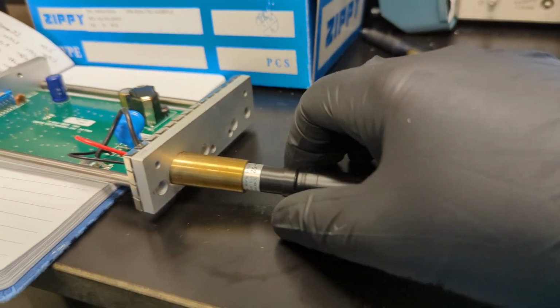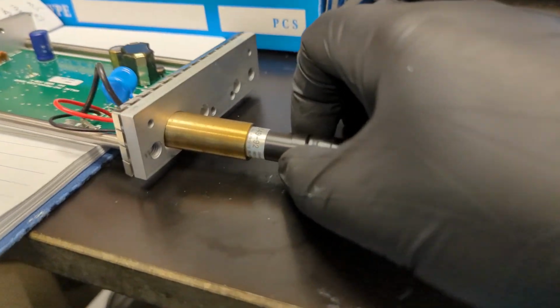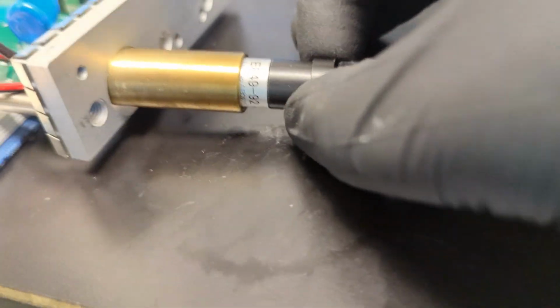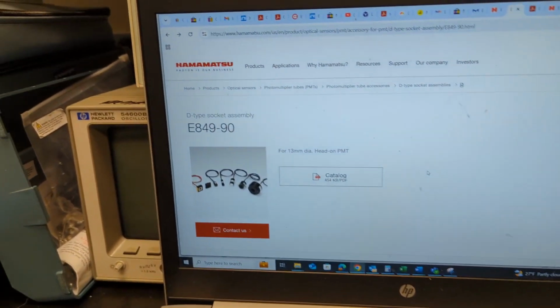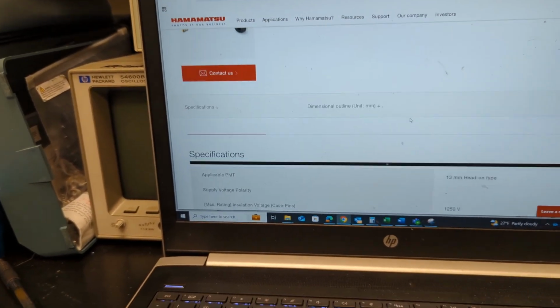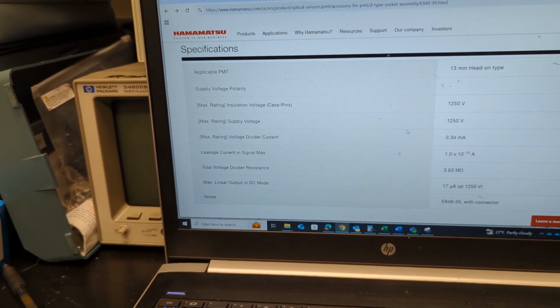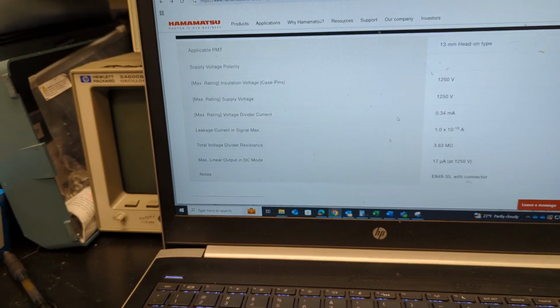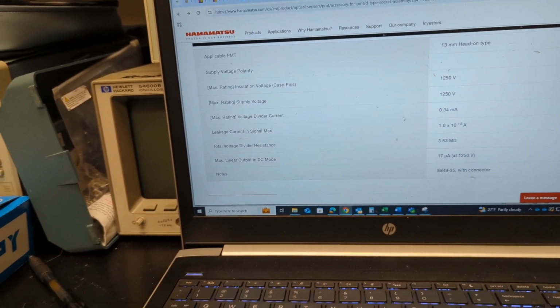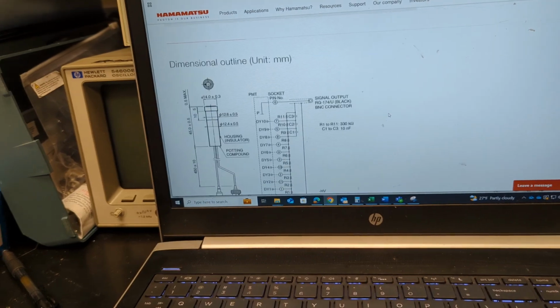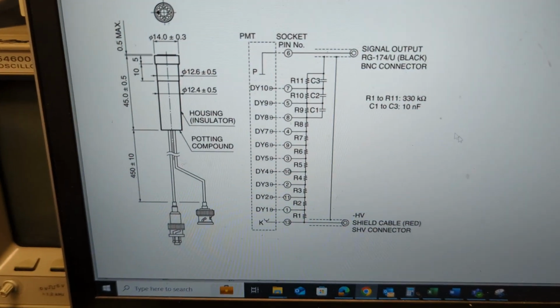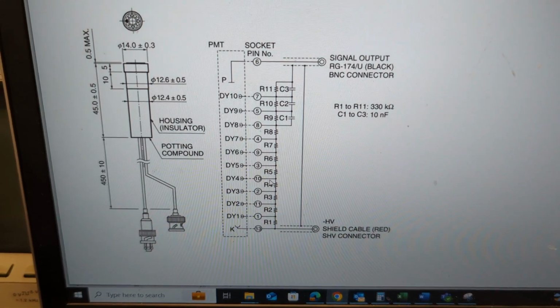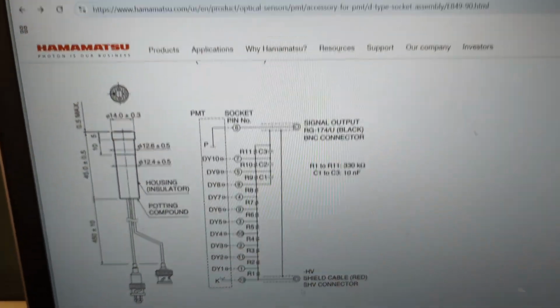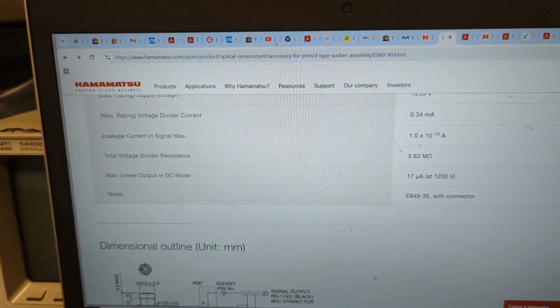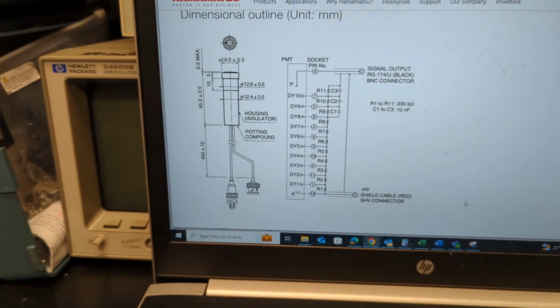you'll notice though that you've got this other adapter here, which is also from Hamamatsu. It's an E849, and they call these D-type socket assemblies. And so these are basically just voltage dividers that ensure that the correct voltage is being delivered to each of the dynodes inside the photomultiplier tube. And so you actually can see how that's hooked up here. This again is just a 11 resistor voltage divider, and it even gave you the total resistance of that divider here at 3.63 mega ohms.